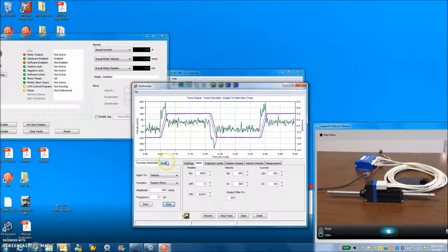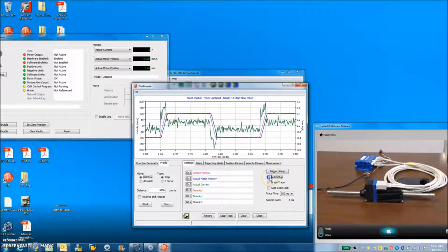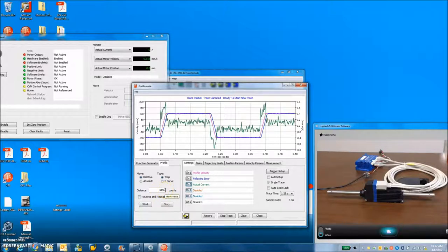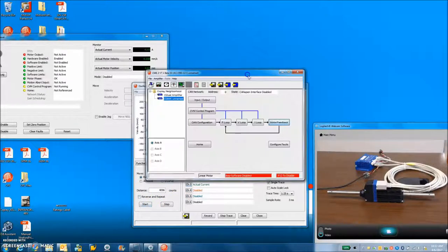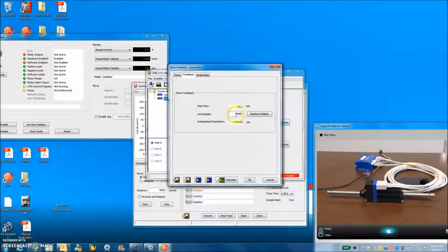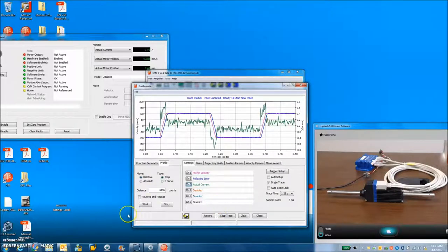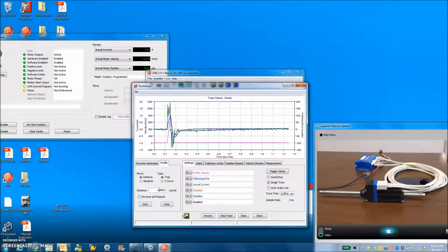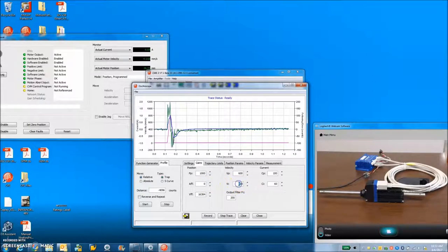And let's stop that. We'll go to a profile tab, auto setup checkbox, channel 3, current actual, and 4096. That's the interpolation off of a magnetic pole pitch, 25.6. So I guess it goes 25.6 millimeters for 6.25 micron repeatability. So just checking out how far we plan to see this thing move. We moved an inch in the forward direction, or 25.4. I could use a little bit more integral here. So let's go back in the negative direction. Let's give it a little bit more integral there.